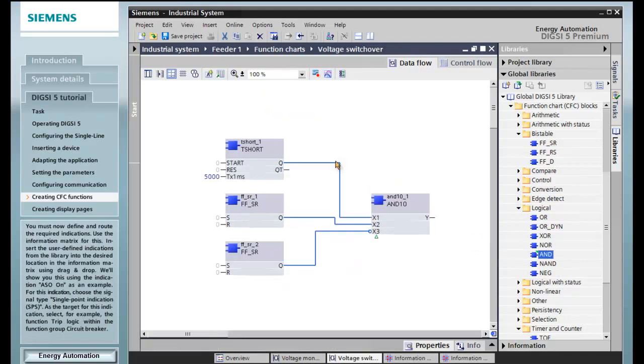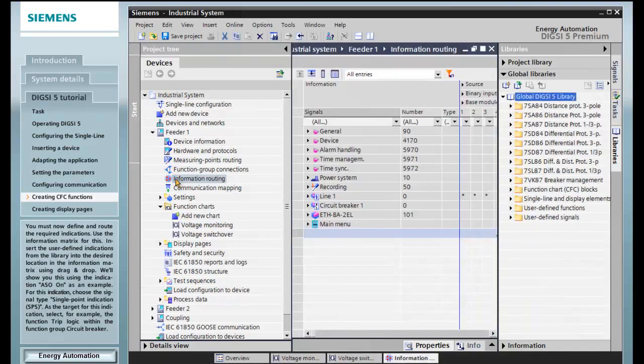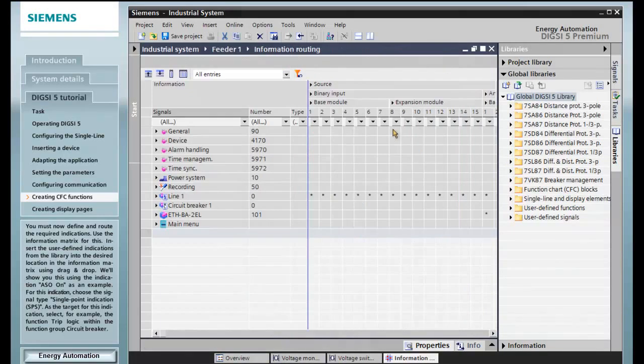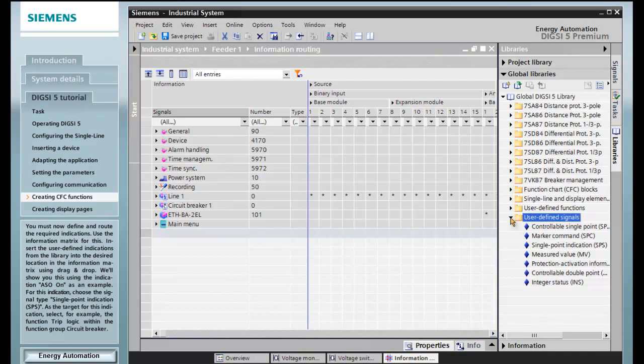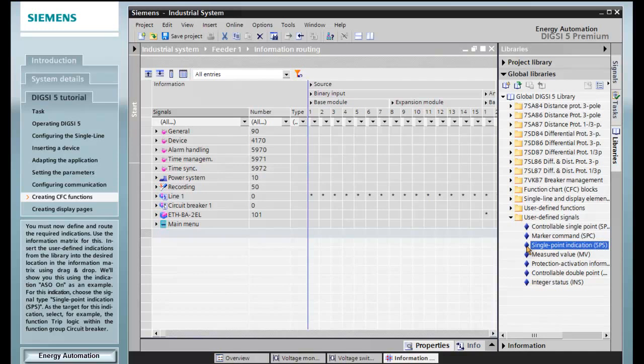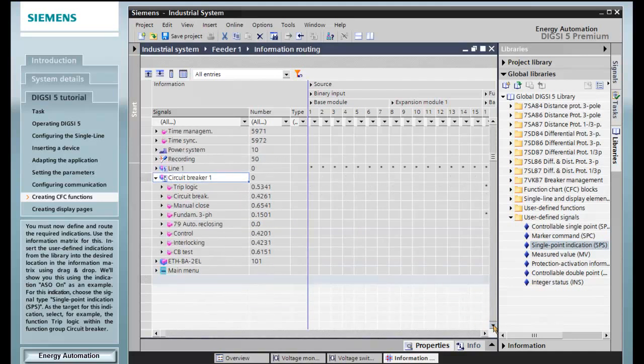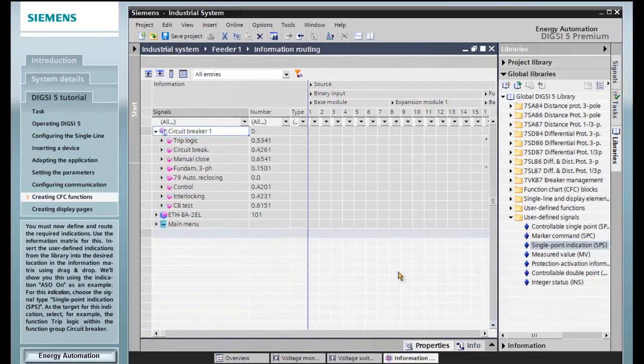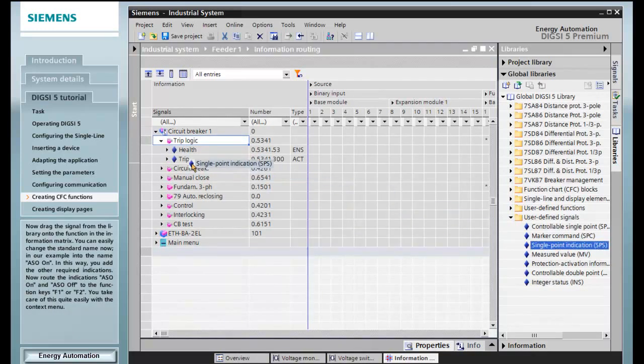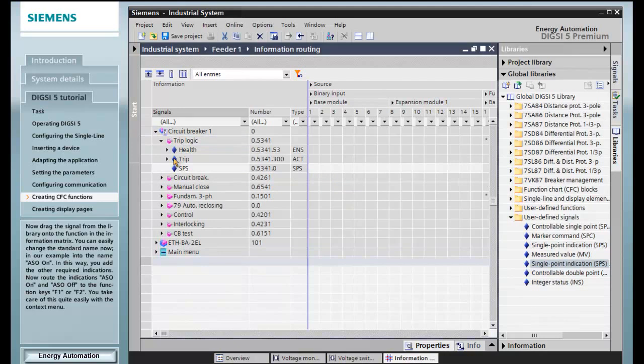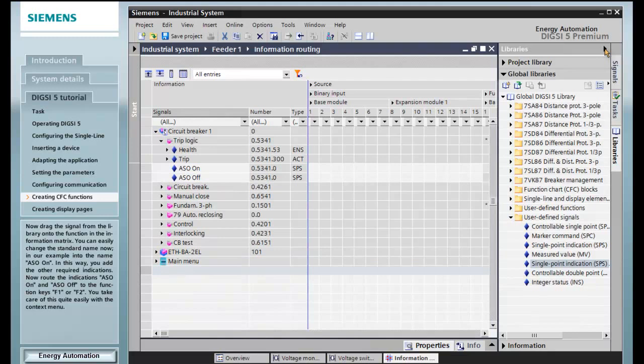You must now define and route the required indications. Use the information matrix for this. Insert the user-defined indications from the library into the desired location in the information matrix using drag and drop. We'll show you this using the indication ASO on as an example. For this indication, select the signal type single point indication SPS. As the target for this indication, choose for example the function trip logic within the function group circuit breaker. Now drag the signal from the library onto the function in the information matrix. You can easily change the standard name now, in our example, into the name ASO on. This way you add the other required indications.